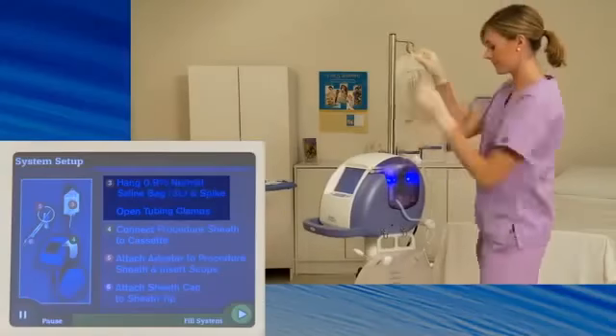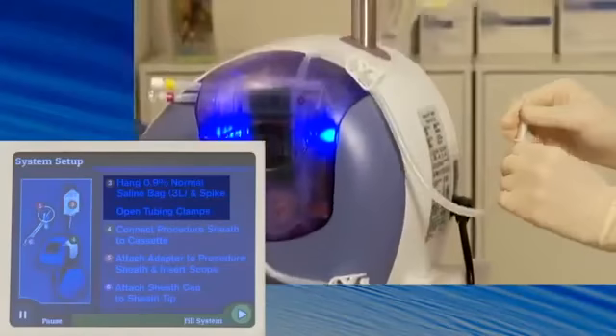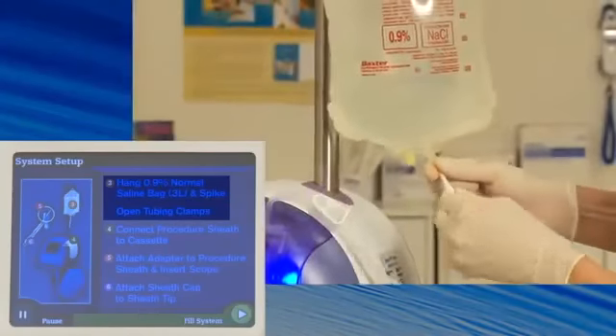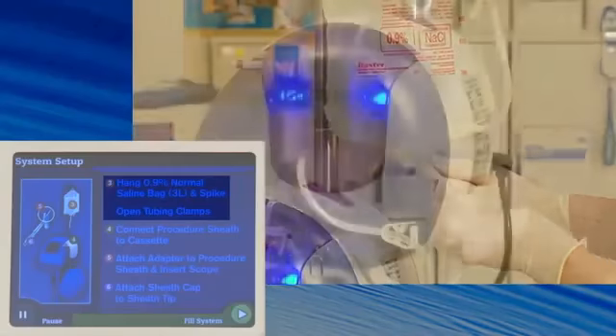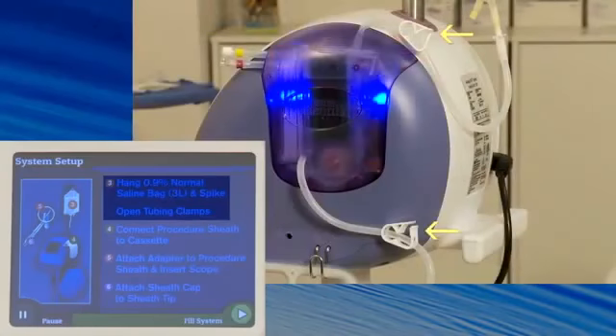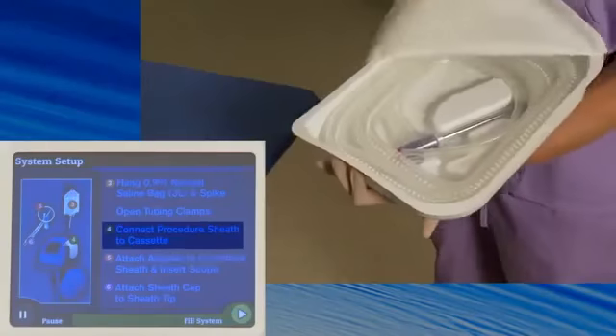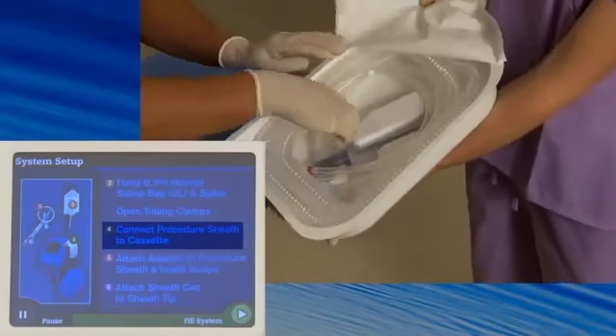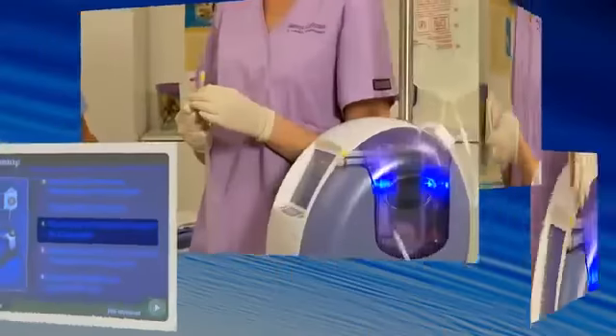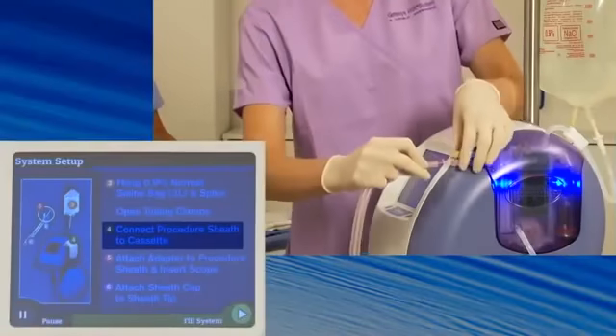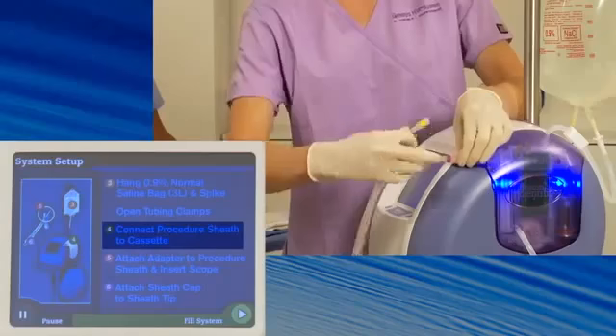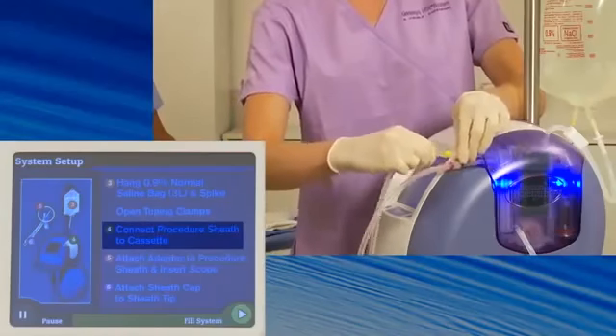Hang a 3-liter bag of saline on the IV pole. Then spike the saline bag. Now check to confirm that the tubing clamps are open. Next, while observing sterile technique, open the procedure sheath tray. Be sure to remove the 2 dust caps from the sheath and the 2 dust caps from the cassette. Connect the sheath's inflow and outflow tubing to match the color-coded connections on the cassette.